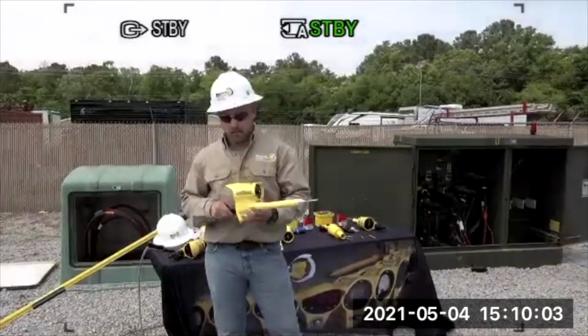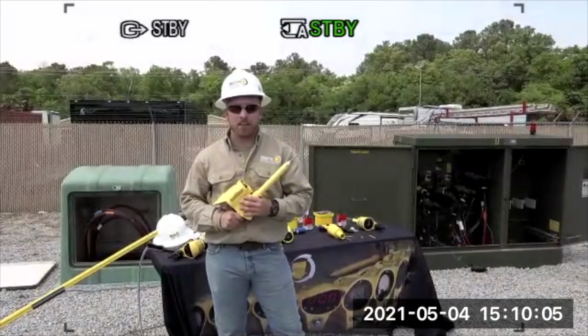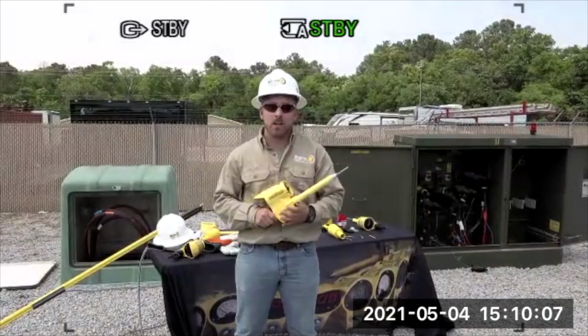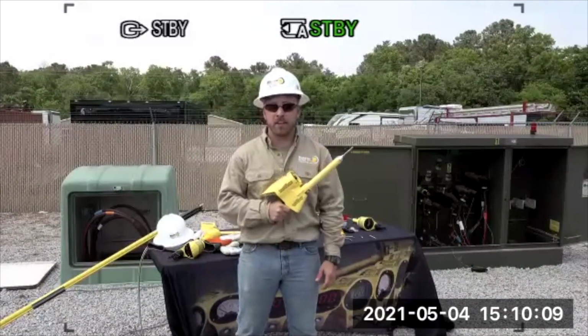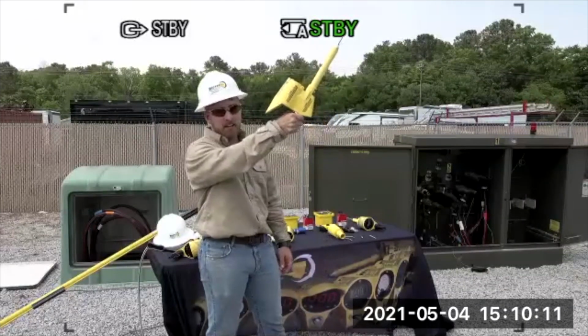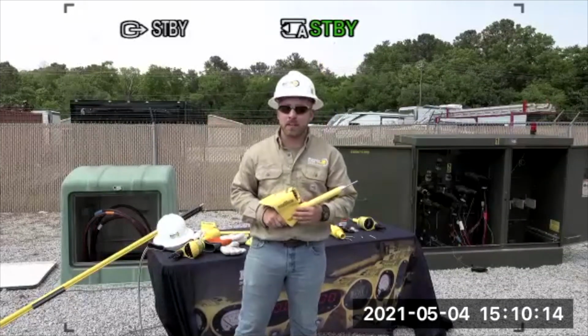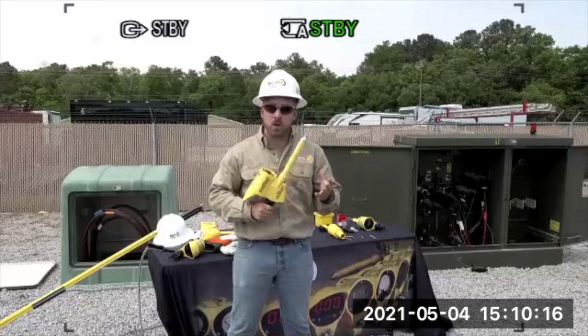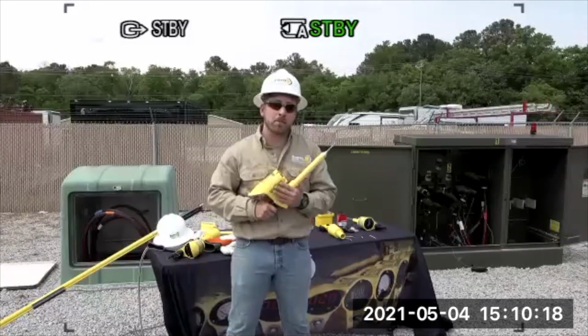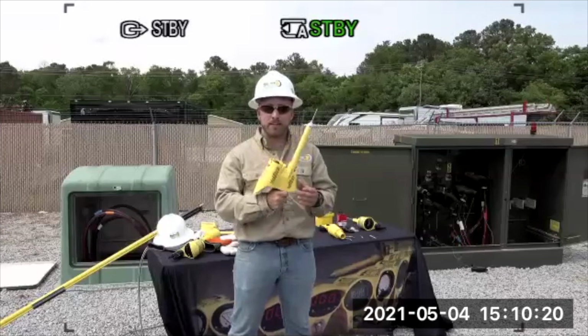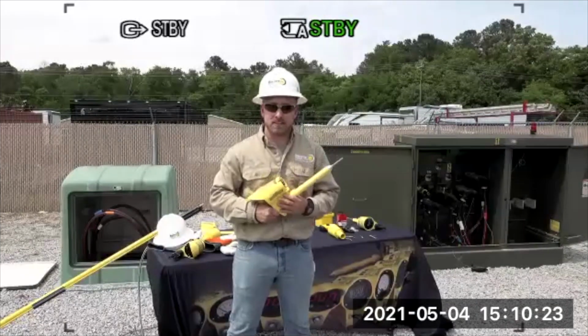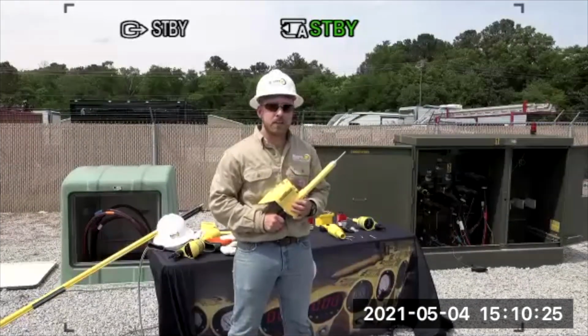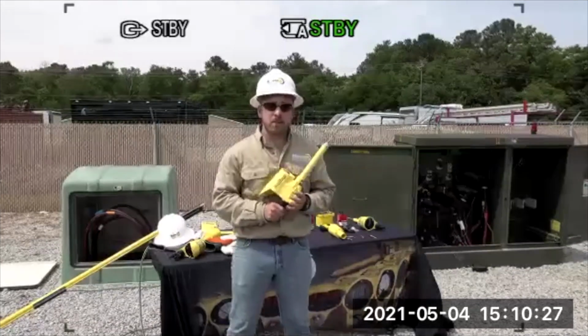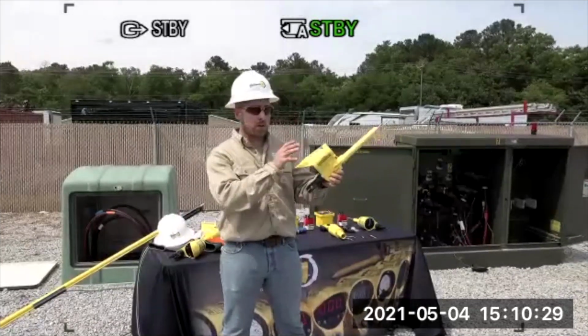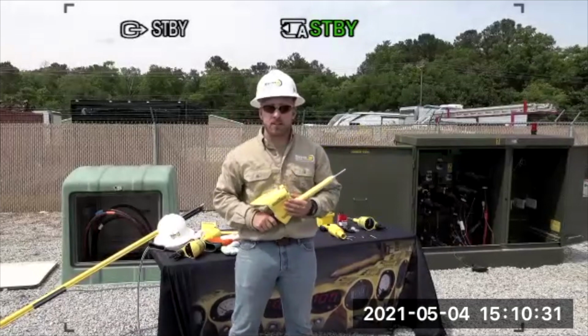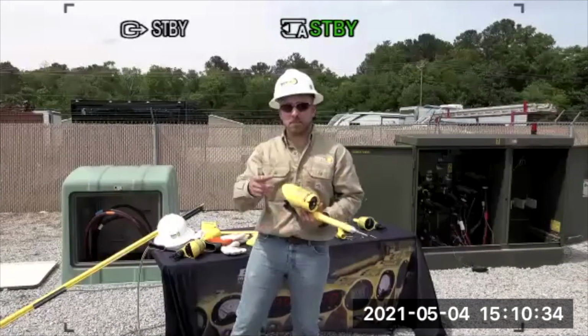Another thing is we hear of utilities holding the meter with their gloved hand like this, going up to the line. That's a big no-no, because what the meter does is couple with capacitance, and when you're holding it like this, you're actually coupling with that capacitance yourself. So we recommend always keeping at least 24 inches back from the meter head with your live line tool. Brent, take over here.